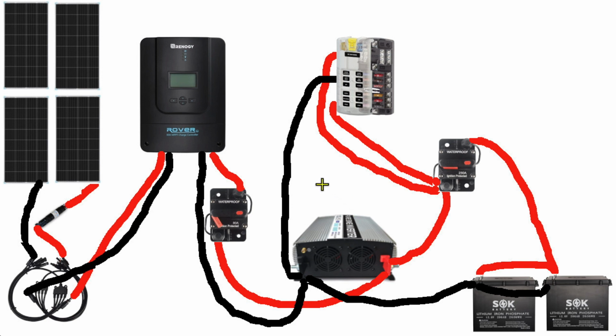So you divide 3000 watts by 12 volts, which gives you 250 amps. So you need a minimum 250 amp circuit breaker. If we multiply that by 1.25 for our margin of safety, that gives us 312.5 amps. So I only have a 250 amp — it hasn't popped yet, but if it does, I'll upgrade this to a 300 amp circuit breaker.